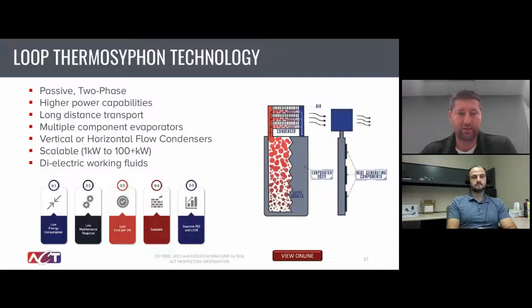What ACT developed and is implementing in the field is loop thermosiphon technology, which takes it to kind of a higher or more advanced level and enhances your heat transport capabilities even further. So same design principles or considerations here. You're evaporating at your heat source and you're condensing at your heat sink. But because you're running in a full loop and it's designed strategically that when you're condensing, you're continuing the path of the loop, you never have the forces interacting. So your vapor is flowing one direction, your liquid's flowing continuously along the loop. In a heat pipe or a typical thermosiphon, those forces would interact. So your vapor would be flowing down the center and your liquid would be returning around the outside, but that creates some inertial forces within it, which limits your overall capacity. So in the case of a loop thermosiphon, you can move more heat in a similar form factor.